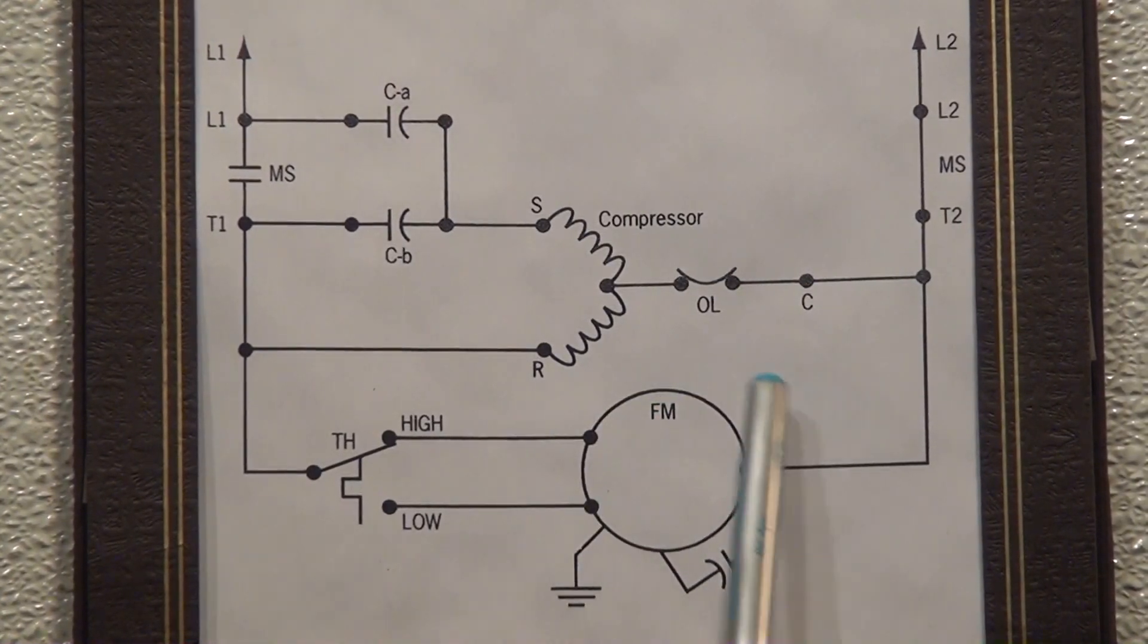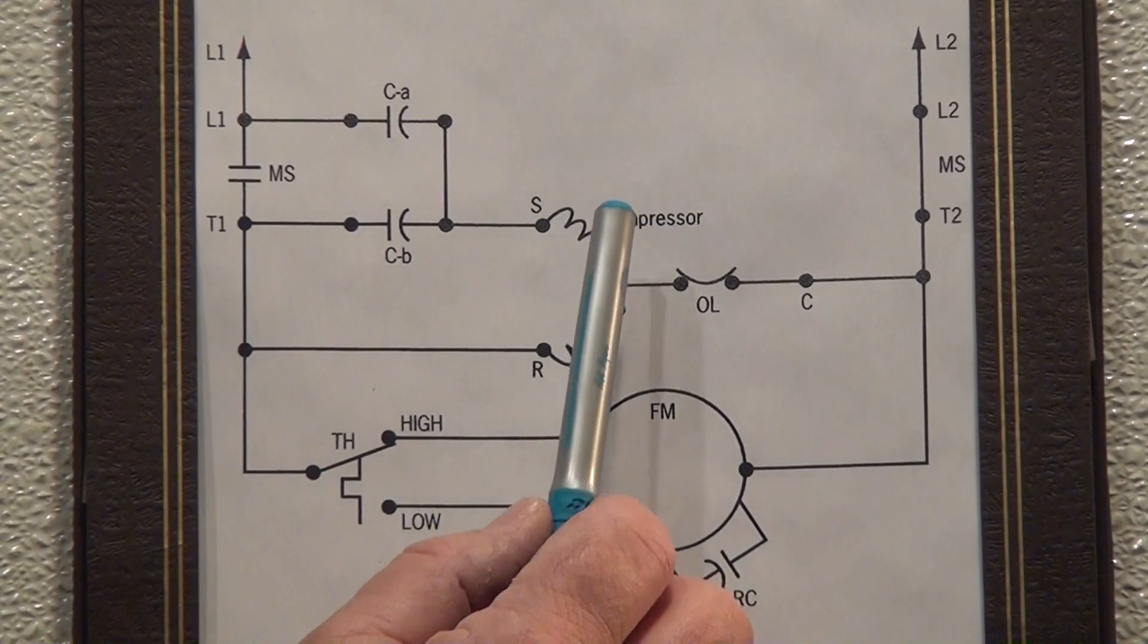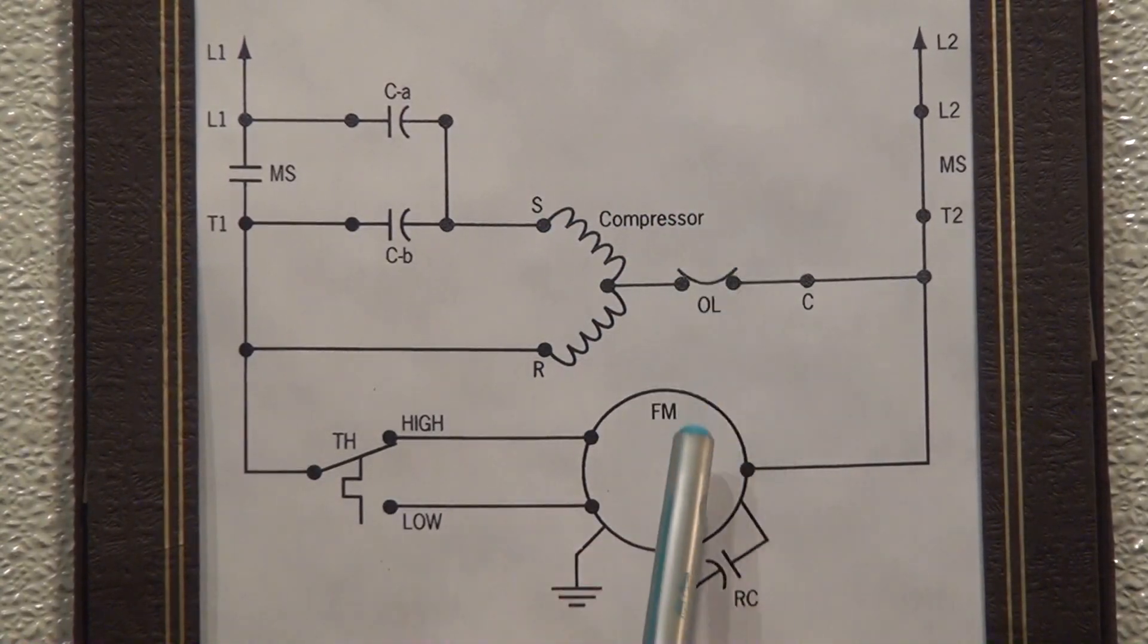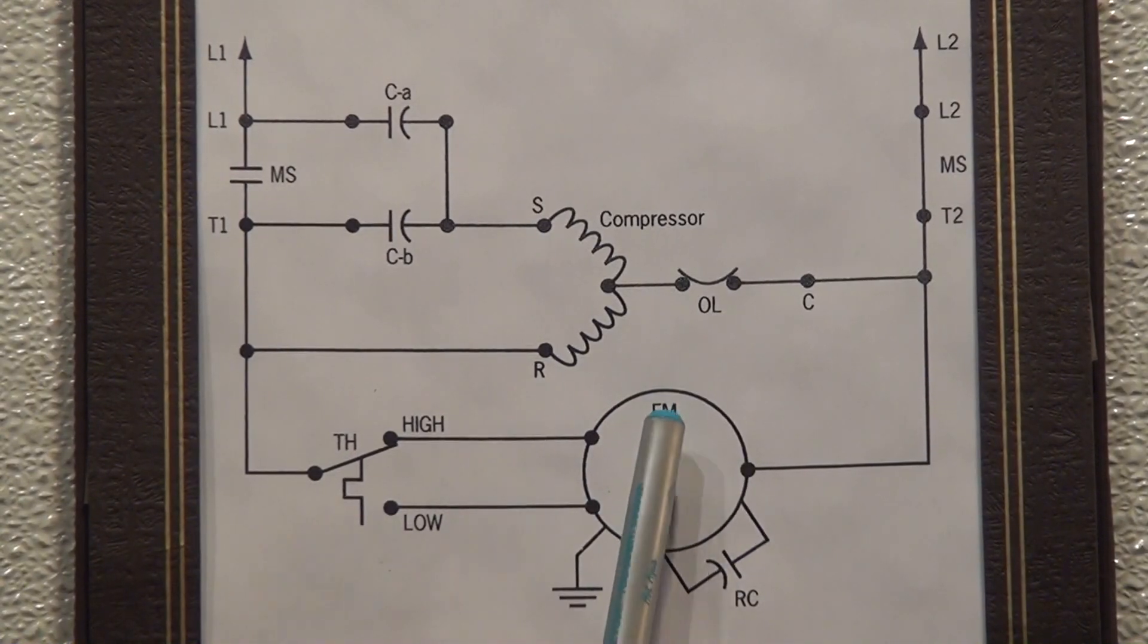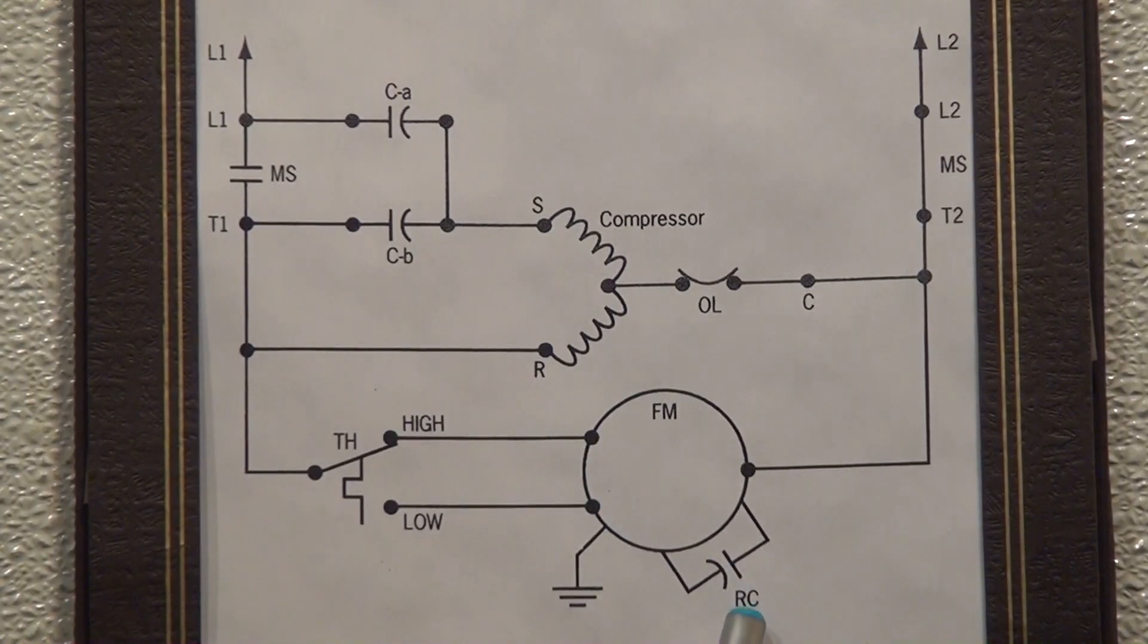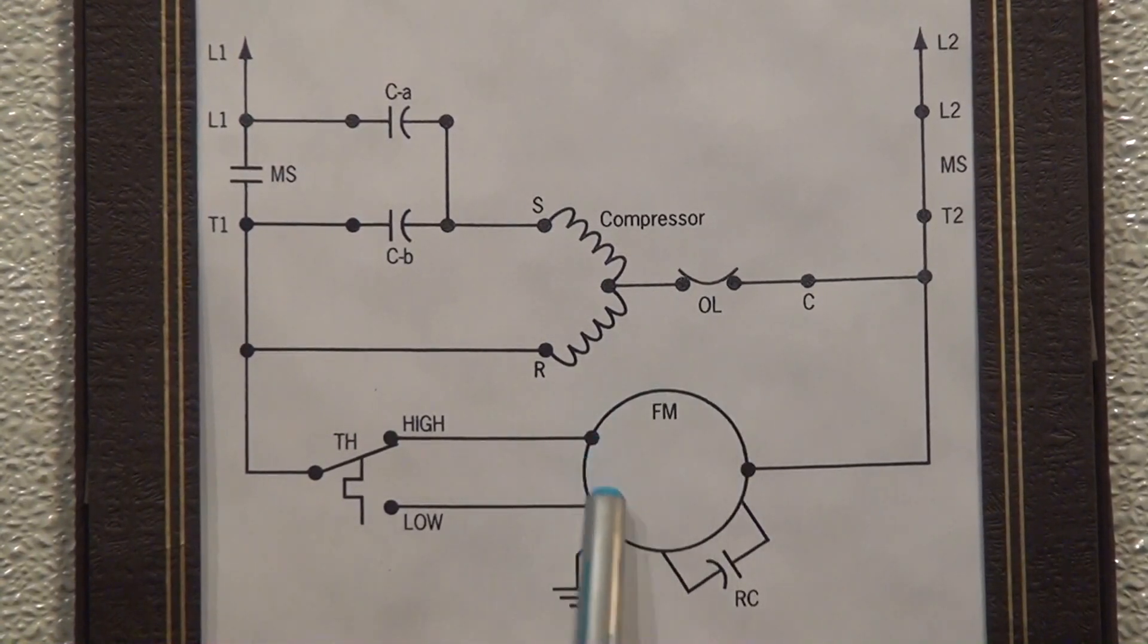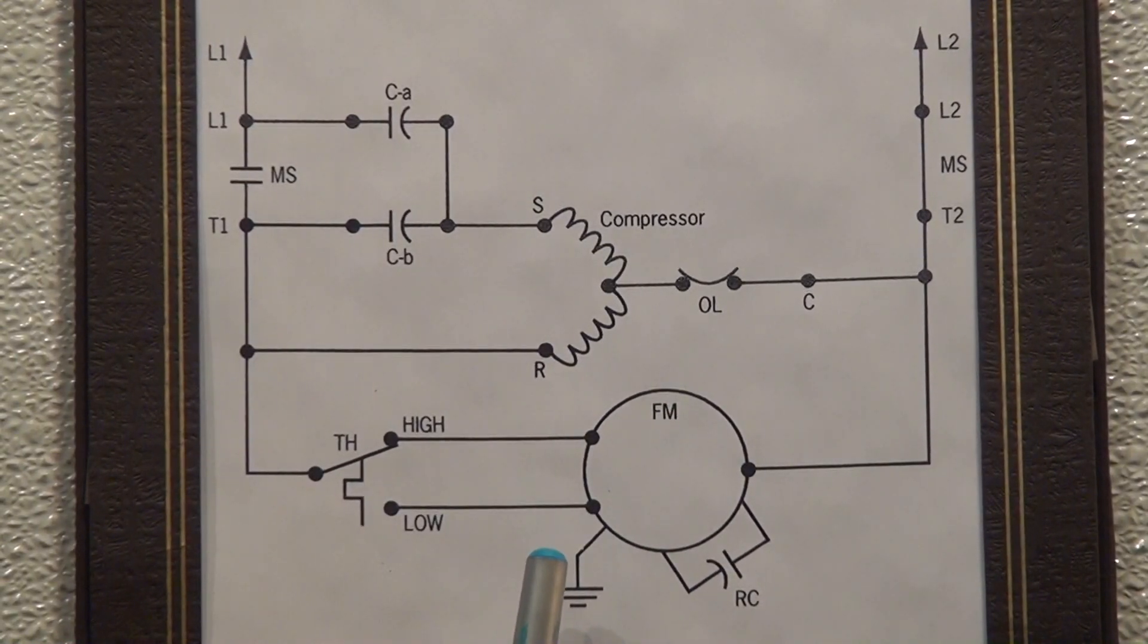Moving on down to this component here, we want to show this component even though it's not part of the problem. The symptoms that we're getting is that the compressor itself is trying to start and kicking off on overload and what we understand is that the fan motor FM in this case stands for outdoor fan motor. This particular outdoor fan motor uses its own run capacitor as you can see here, and this fan motor in our situation is running okay but it's part of the diagram so we want to explain it.